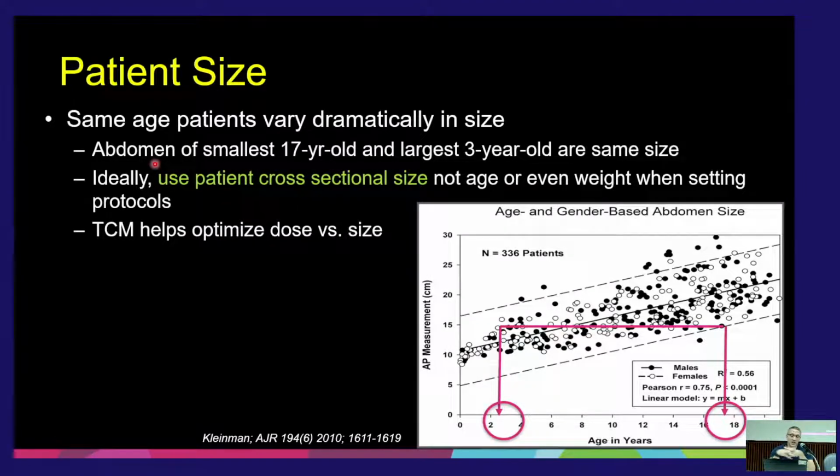So this question came up yesterday while we were over in the hospital. The question was, should we use weight or size when we calculate different automatic profile or automatic protocol estimations? So GE and Siemens, which are the two scanners we were looking at across the street, they both basically do this. They both take into account the patient size.